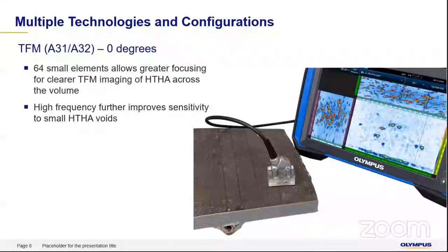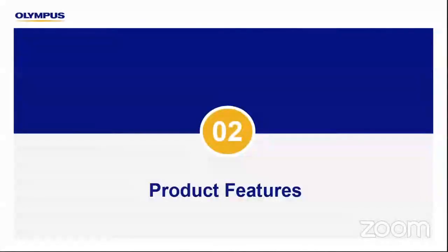The A31 and A32 probes are our standard weld series probes, but they have been introduced specifically for HTHA with a higher frequency. This gives much more improved sensitivity on very small or fine HTHA voids.